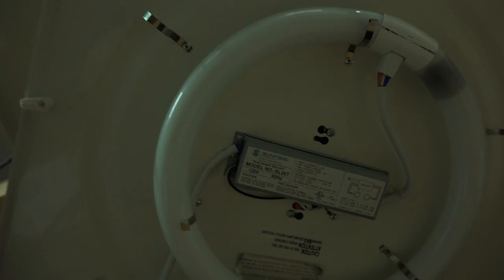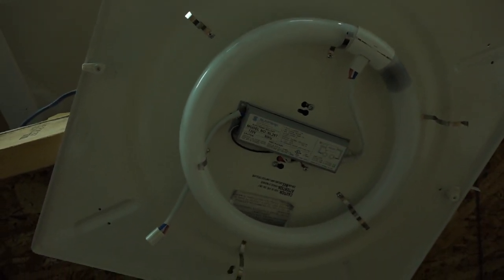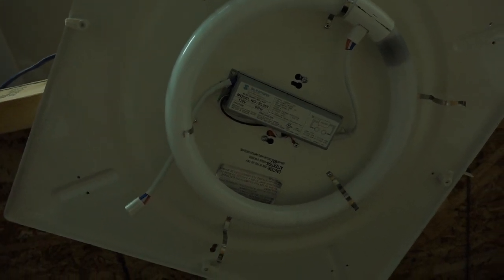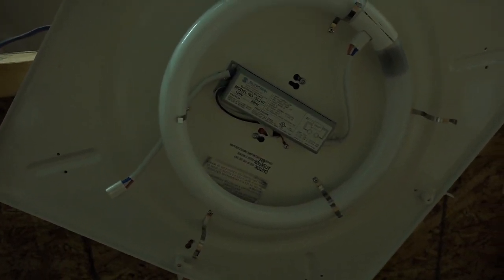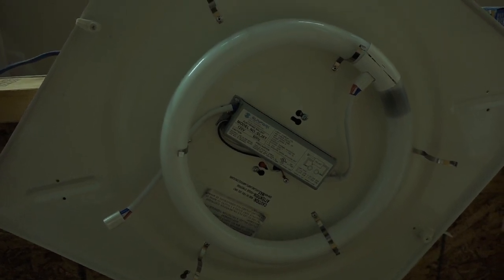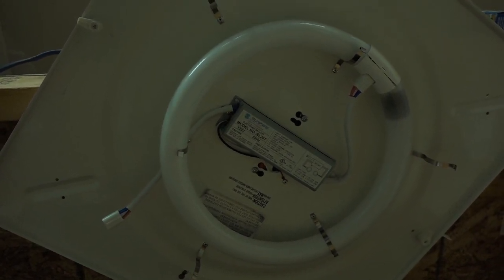So as you can see here, I've got this mocked up here. We've got a ballast here, and then you have to have two bulbs plugged in order for it to work. So both bulbs have to be plugged in and functioning in order for the ballast to output power and ignite the bulbs. Fluorescent light bulbs work by sending a high inrush of voltage into the inert gas inside the bulb. This then illuminates the gas in order to produce light.